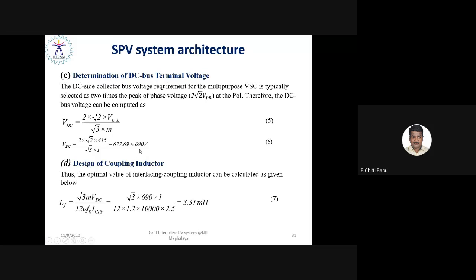So the DC link voltage is imposed at 690 volt, because as you use pulse width modulation, the effective DC link utilization is about 78.5%. So the DC link voltage should always be at least 125% of the line to line three phase AC voltage, right? And the design of the coupling inductor is very important, because the inverter output current may have a DC component as well.